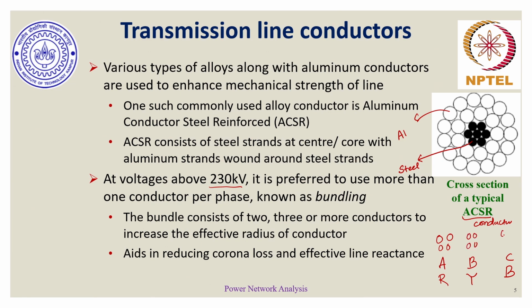So let's say if I have to draw a 4 bundled conductor, with each bundle representing one phase, then this is one such bundle. Often you would see such an arrangement in overhead transmission towers operating beyond 220 kV, 400 kV, where there are usually multiples of three, 12, 15, 18, 21 conductors running in parallel. And if we were to assume that 21 conductors pertain to one phase, there are bundles which pertain to one such phase.